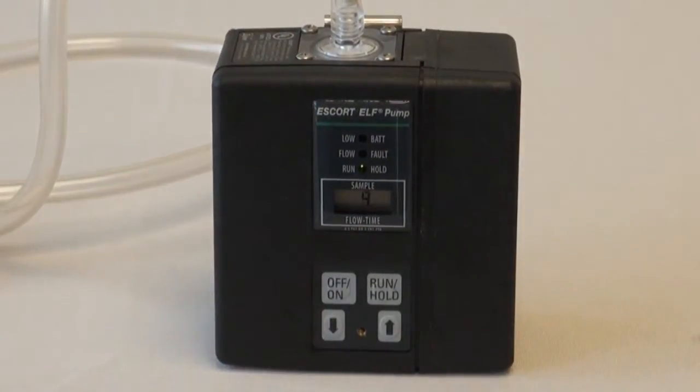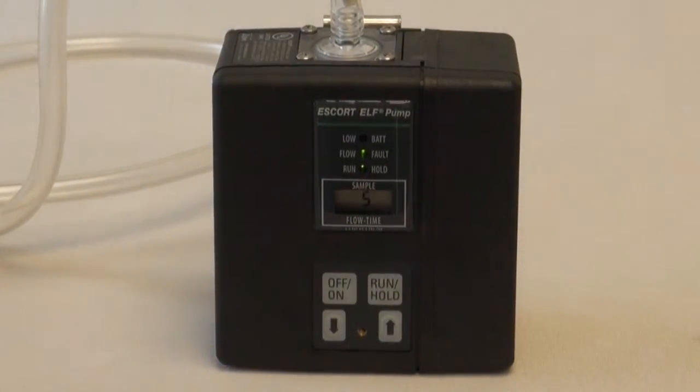Failure to release both buttons will turn the pump off. The LCD display will now show CAL, and a countdown sequence will begin from the number 9 to 0. After the countdown, the LCD will alternately display CAL and 2.5 liters per minute.